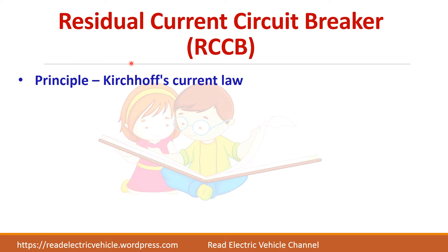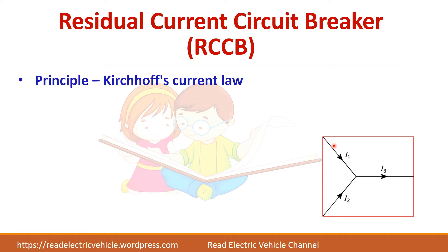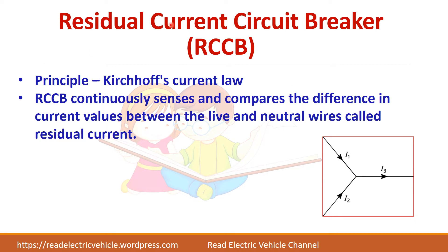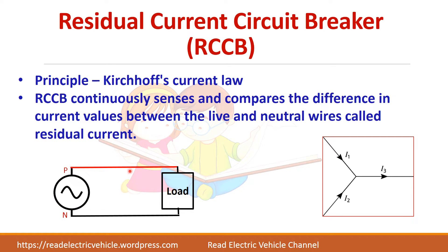The basic principle behind RCCB is Kirchhoff's current law. According to this law, the sum of the current entering a node should be equal to the current leaving the node. In this case, I1 and I2 are entering the node, so they should equal I3. This RCCB will continuously check the current between the phase line and neutral line. The AC supply is supplying a load, and the load draws some current which passes through the load and returns back.